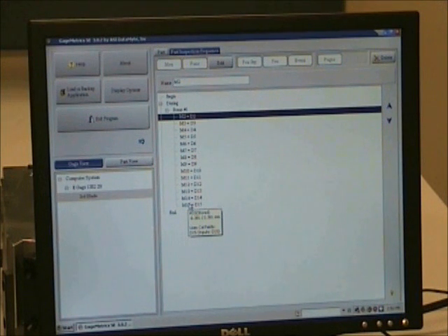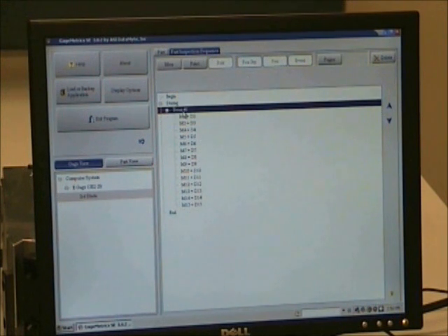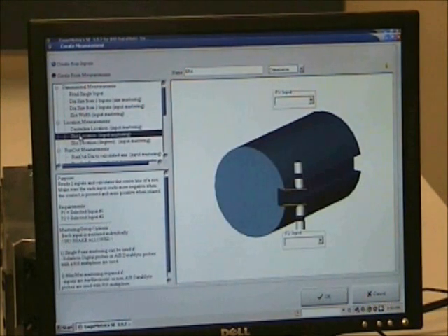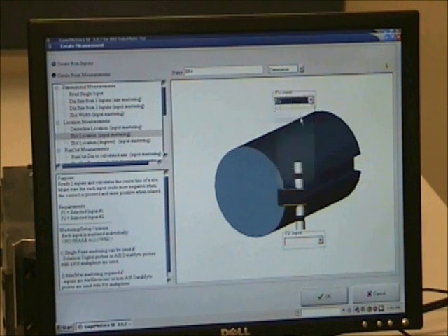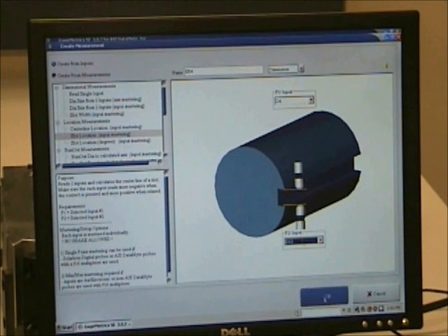You can add another measurement very simply by going to your event, clicking on the measurement button up there, and creating a name, calling it whatever you'd like. I could call that ER4 if I wanted to. It wouldn't really matter. I come over to select what probe I want to use, for instance, probe D4. If I want to come over on the side here and select a slot, I can select D4 minus D12, and that will give me that slot width.